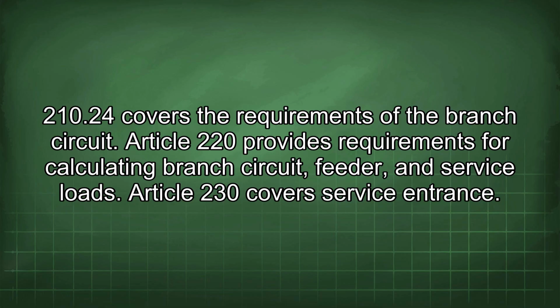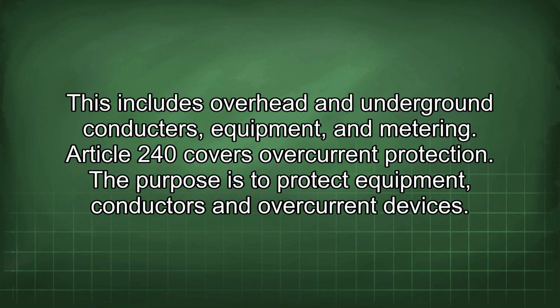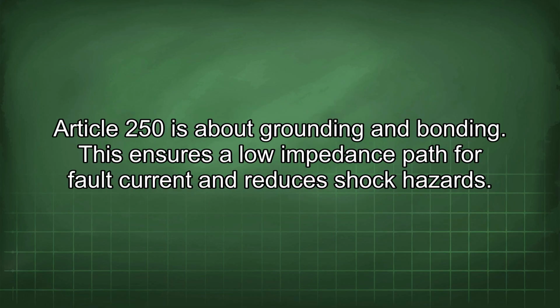Article 220 provides requirements for calculating branch circuit, feeder, and service loads. Article 230 covers service entrance. This includes overhead and underground conductors, equipment, and metering. Article 240 covers overcurrent protection. The purpose is to protect equipment, conductors, and overcurrent devices. Article 250 is about grounding and bonding. This ensures a low impedance path for fault current and reduces shock hazards.